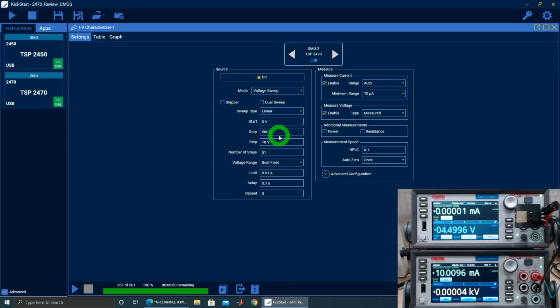Now there is one limitation that I wish was a little bit different. The threshold for where the maximum current of the SMU 2470 jumps from 100 milliamp to 10 milliamp is at 200 volts. It would have been really nice if that transition wasn't 200, it was more like 500, because if I want to measure anything up to 100 milliamp, I'm limited to the 200 volt range. As soon as I go above that, I have to do 10 milliamp. So there's a bit of a limitation there. That's just the way they've chosen to partition those voltages. That's the limitation of the instrument.